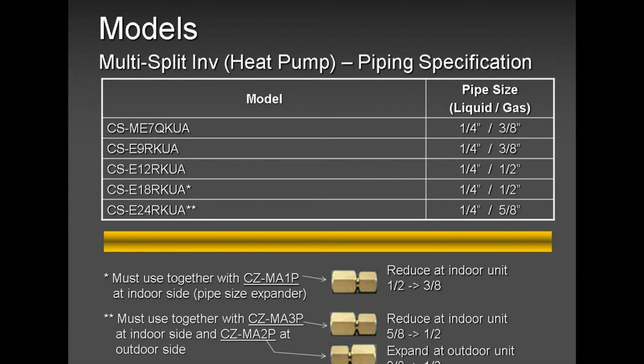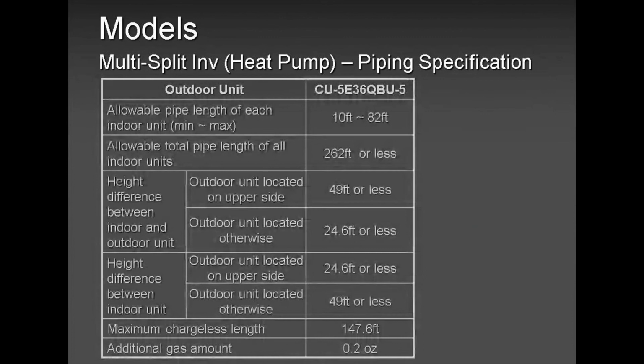So what are you going to do if you have a 12,000? You are going to run 3/8 and 1/4 all the way to the indoor unit. And when you get to the indoor unit, you will use an adapter that will be from 3/8 to half inch. I know with Mitsubishi and other companies, you will run half inch and quarter all the way to the outdoor unit and do adjustments there. No, please do not do that.